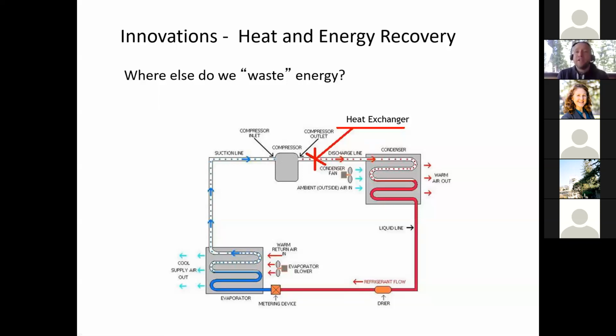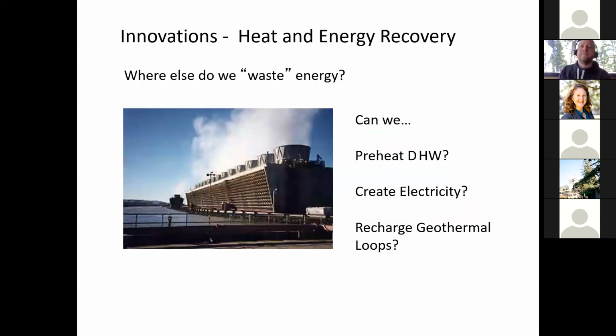On a really good project, you would add a little heat exchanger there before the condenser line and pull some of that heat off. You could use that heat to preheat domestic hot water. Kitchens and restaurants use a lot of domestic hot water, so you could use the refrigerators to help heat the hot water, which sounds counterintuitive but works really well. Every project often has some sort of waste energy we can recapture for a really valuable reason.